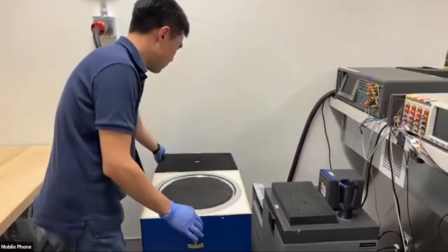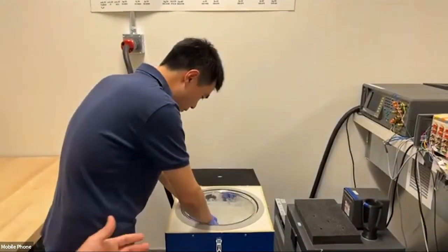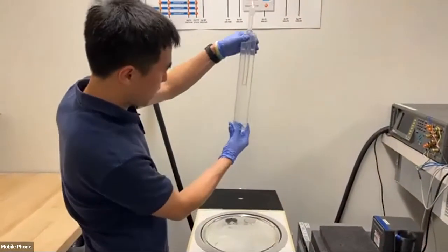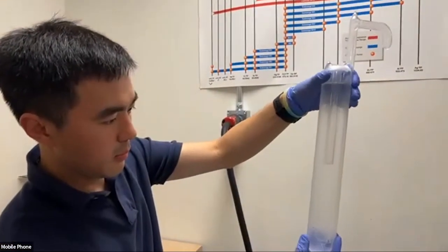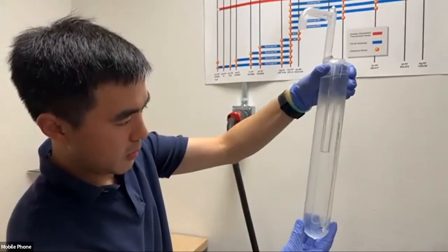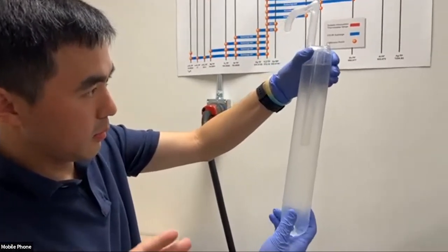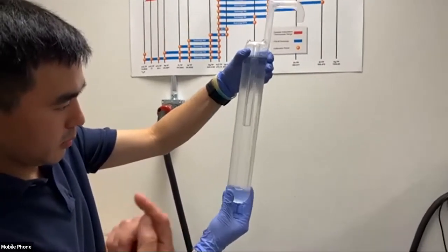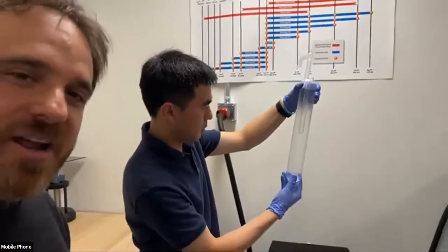So this is a dewar where we keep our cells conditioned. For those of you that have never seen this, this is what a triple point of water cell looks like. So water is actually living here in its 3 natural phases: its liquid phase, its solid phase, and its gas phase. And when the triple point is correctly realized, we have a mass of ice that can just circle around the center tube, which is where we insert our SPRT.